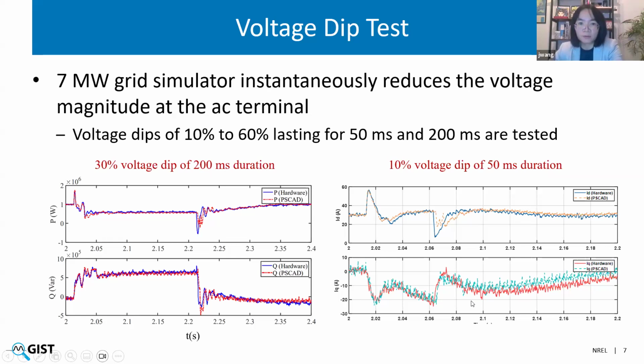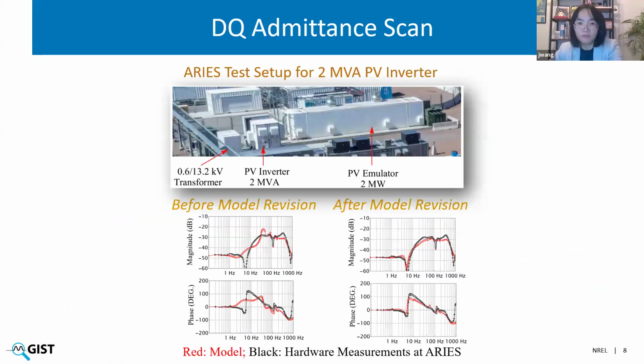There are many others. Because of the time, I will just show another one, which is the DQ admittance scan using the tool that Xiayao has. So we have a preliminary test. You can see before model revision, the impedance scan has some discrepancy in both magnitude and phase angle. But after model revision, as I mentioned, including the DC transformer and also some inverter tuning, we finally make the impedance scan plot match pretty well. So this gives us assurance that the grid following inverter PSCAD model matches the hardware inverter very well. So this is good news.